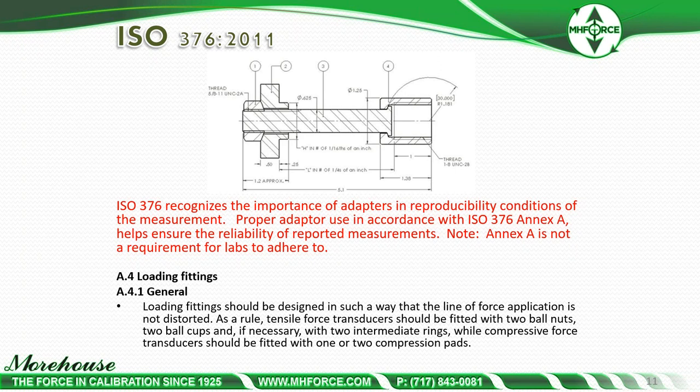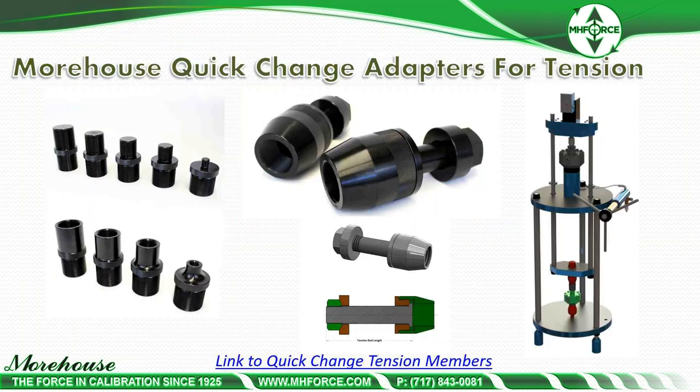ISO 376 Annex A section A.4.1 states that load fittings should be designed so the line of force application is not distorted. As a rule, tensile force transducers should be fitted with two ball nuts, two ball cups, and if necessary two intermediate rings, while compressive force transducers should be fitted with one or two compression pads. Here are some of the adapters Morehouse manufactures.